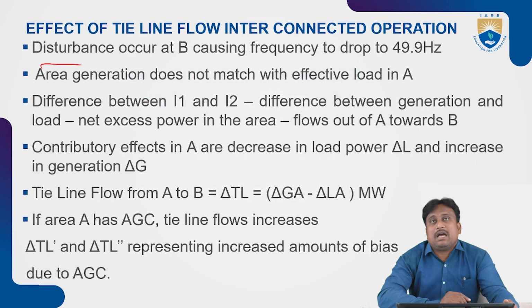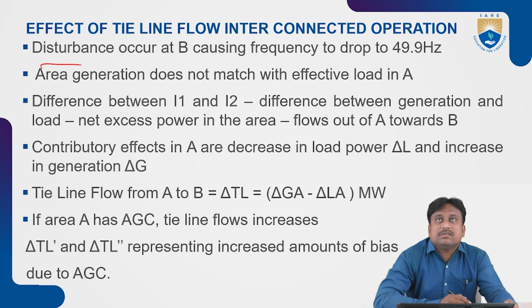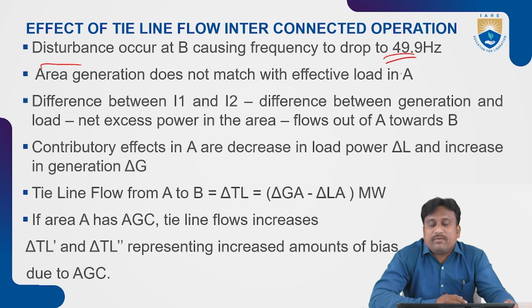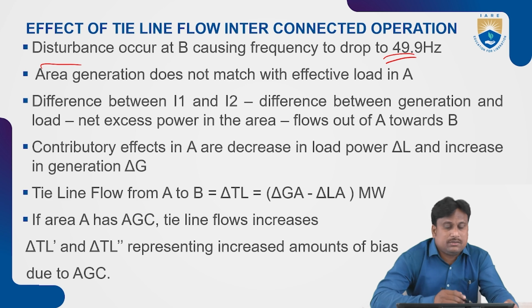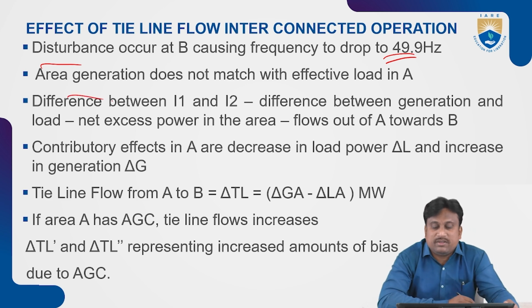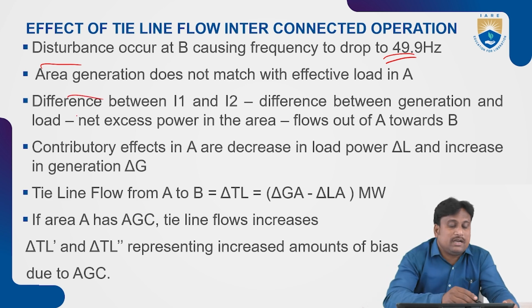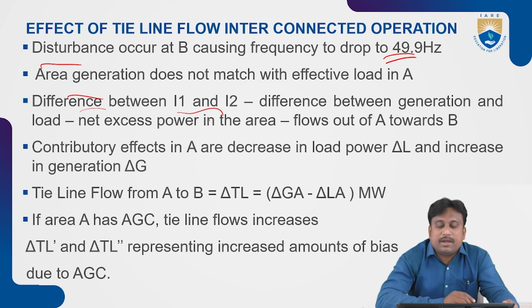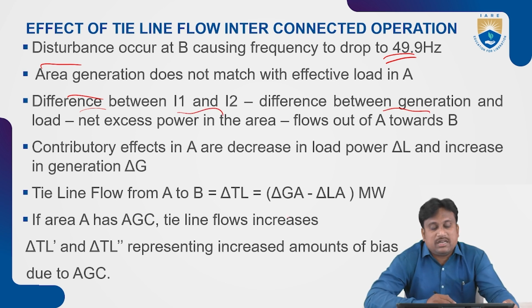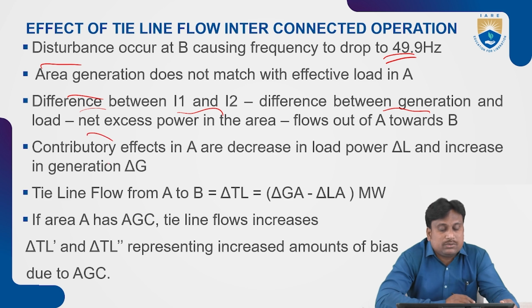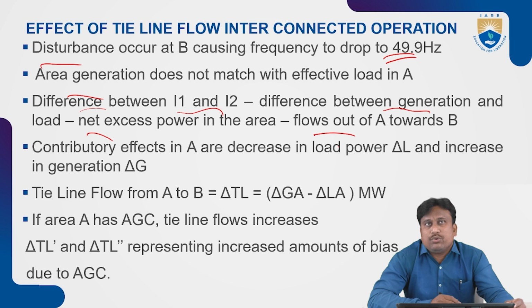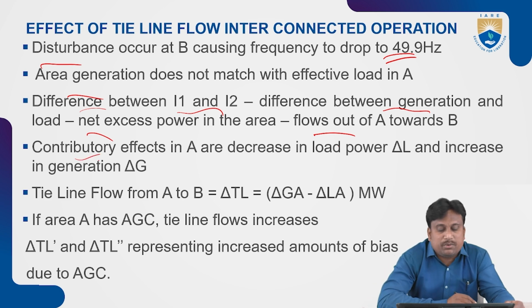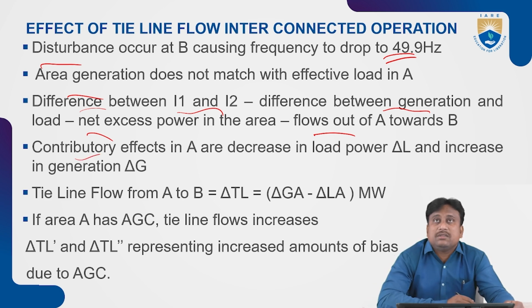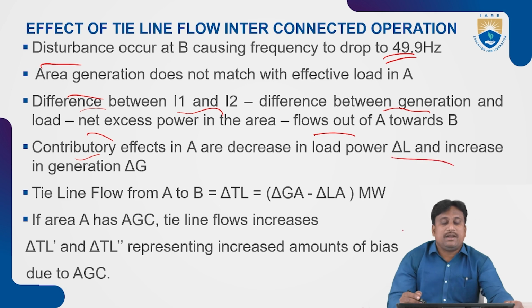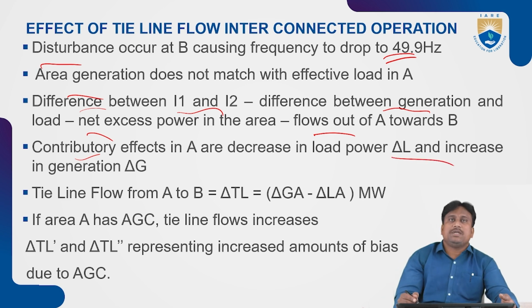So some disturbance occurs at B, causing the frequency to drop to a level of 49.9 Hz. So area generation does not match with the effective load in area A. The difference between generation and load may give us net excess power in the area, so that flow out from A towards B is going to take place. As a contributory effect in area A, a decrease in the load power, delta L, and an increase in generation, delta G, is going to take place.